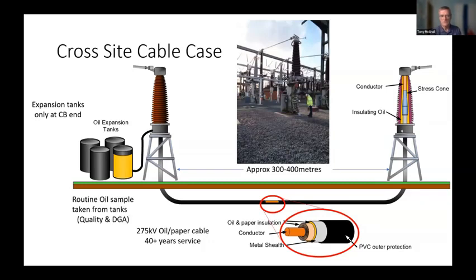Thank you. We also look for oil quality. So we had a lot of experience with cables. Cables at National Grid UK were the largest single asset in value. So if we looked at power transformers, we had more money in cables. Usually people think it's transformers. We had a lot of experience with using these cables in a variety of locations, in tunnels, in direct bury, and so on. The main ring around London was a 400 kV cable. So that was a lot of experience that we had with dealing with issues with cables. So we knew about DGA, we knew about oil quality. So next one, please.